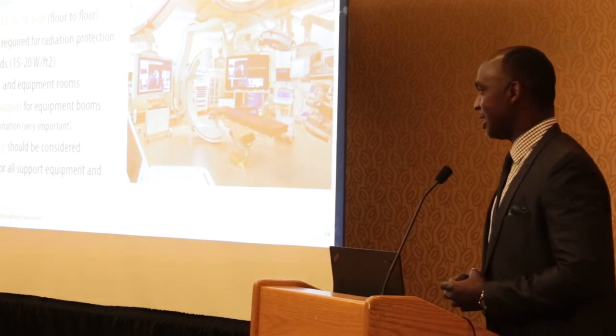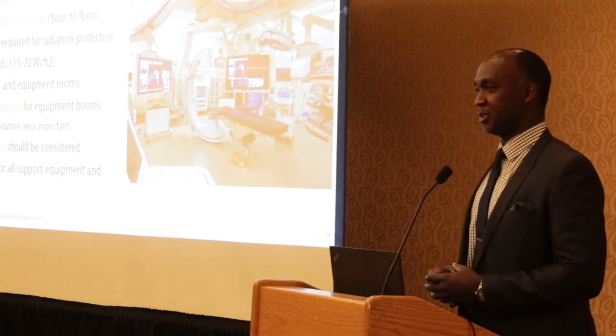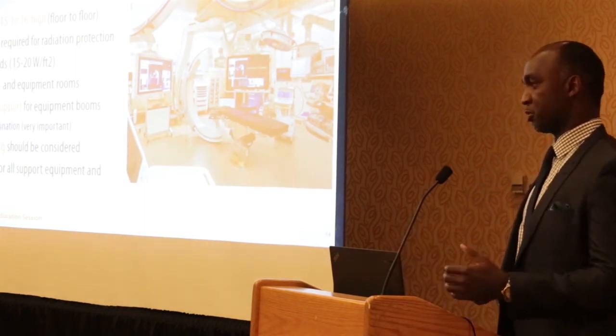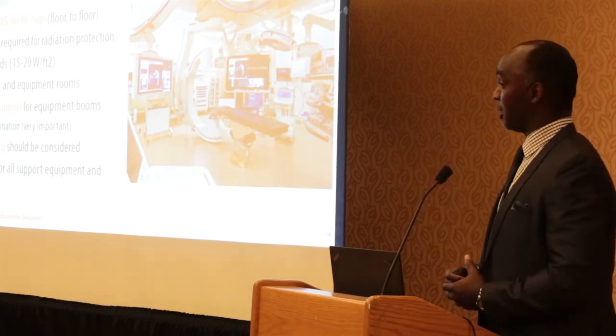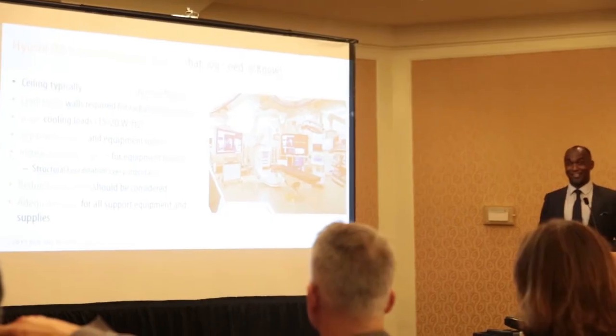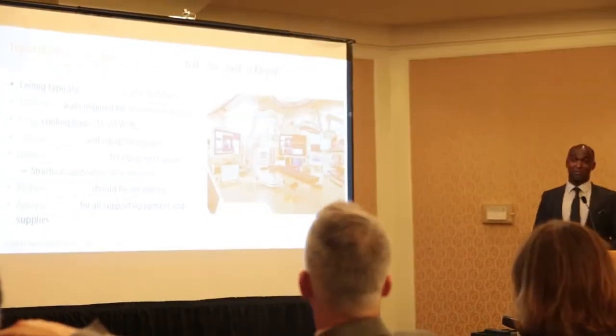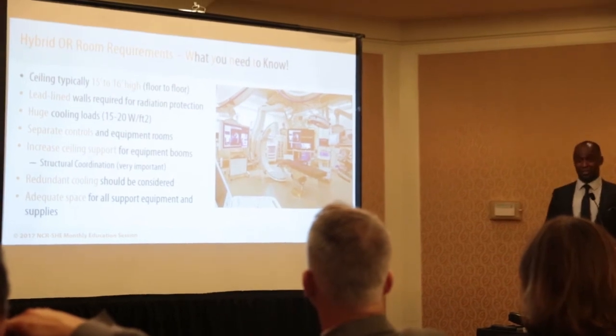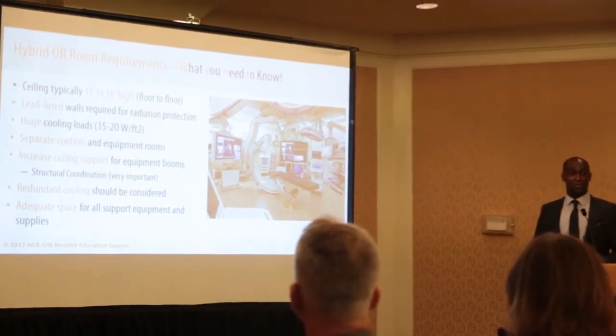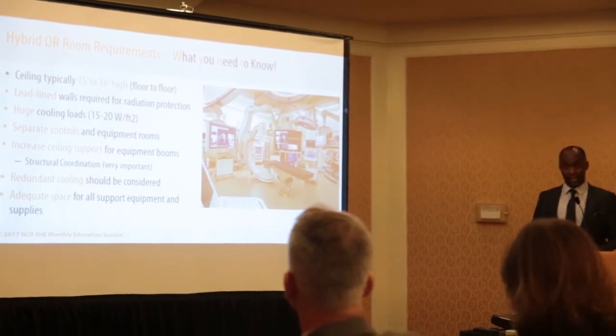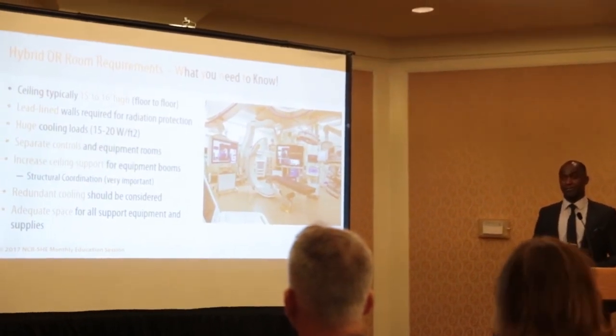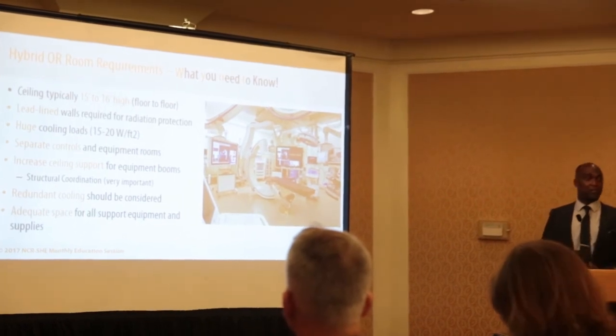You're still trying to get all this down to 65? Oh well, we're going to talk about that also in terms of the temperature, because the code says 68 to 75, and that's the minimum that's required. The temperature of your OR depends on what your surgeon wants your OR to be. It has nothing to do with the code. So yes, it's 68 to 75 that ASHRAE 170 2013 says, but it's what your surgeon wants it to be. They're the leaders, and they will come and tell you that they want 62 degrees in their OR, and that's what they want it to be, and it's non-negotiable. And I've seen that a whole lot in spaces that we've designed.